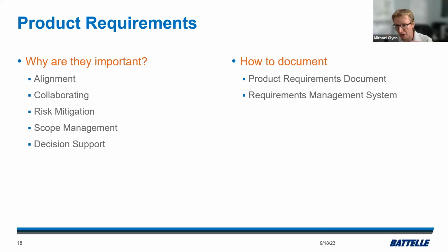In terms of how we document it, obviously there is going to be a product requirements document, although they're called numerous different names, that fundamentally captures the requirements for the product. Quite often they'll be captured in some sort of requirements management system, but that depends on the complexity of the device that you are developing. Simpler systems might use Excel, and we certainly do that from time to time. But for more complicated systems, when there's a lot of tracing to keep track of, a requirements management system is invaluable.